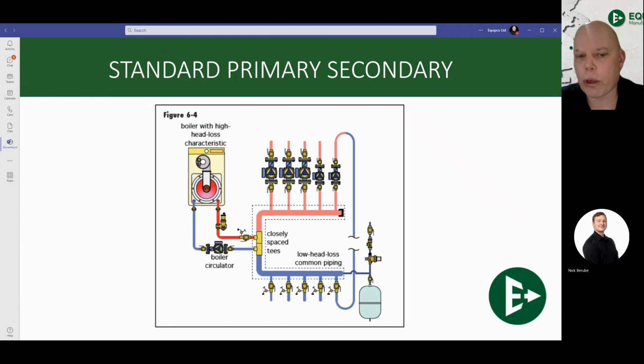So you've got the boiler here, then we're going into a set of closely spaced tees. This is essentially a primary secondary system, where our primary loop is in the boiler and our secondary loop is the system. That closely spaced tees is what separates our primary from our secondary. You also see right underneath the boiler, that's a high efficiency air separator.